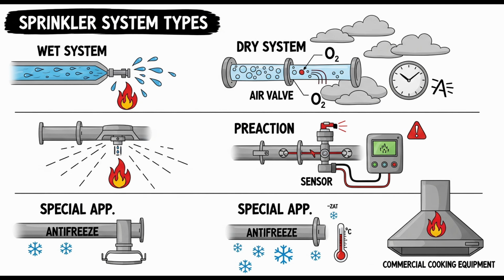Exactly. Or they're used where a fire needs very rapid and widespread water application, which is more the territory of deluge systems. Pre-action is also common in cold storage freezers, as we'll discuss later, because it keeps water out until absolutely needed. And deluge systems? Deluge systems use open sprinkler heads, no heat-sensitive element. They're for high-hazard areas needing total flooding quickly, like aircraft hangars or chemical processing areas.